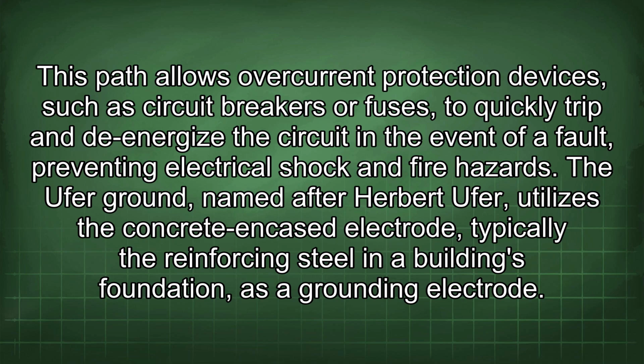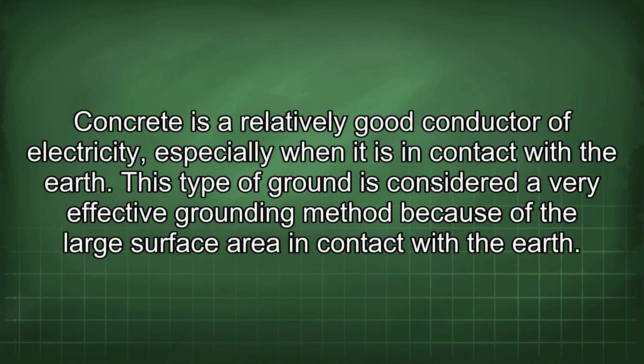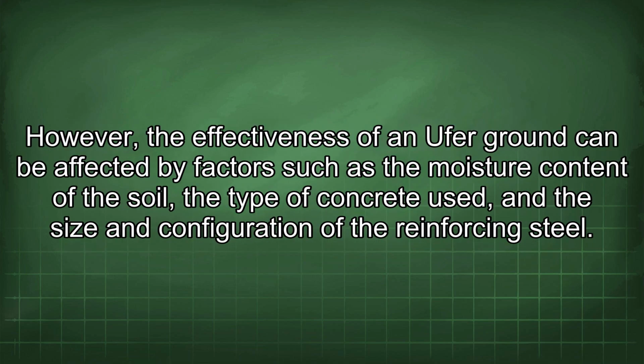The Ufer ground, named after Herbert Ufer, utilizes the concrete encased electrode, typically the reinforcing steel in a building's foundation, as a grounding electrode. Concrete is a relatively good conductor of electricity, especially when it is in contact with the earth. This type of ground is considered a very effective grounding method because of the large surface area in contact with the earth. However, the effectiveness of a Ufer ground can be affected by factors such as the moisture content of the soil, the type of concrete used, and the size and configuration of the reinforcing steel.